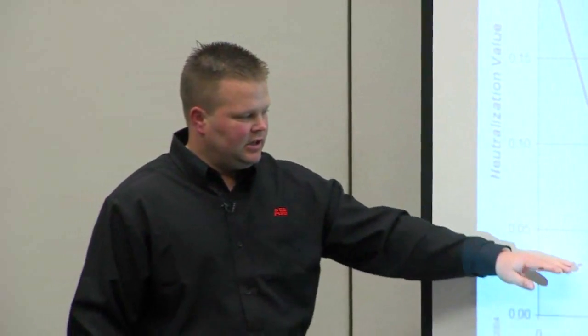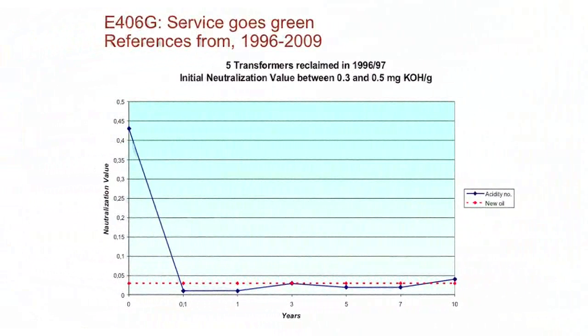So as you can see, over time, after the first month, it was well below the normal acceptable acidity level, and then it increased slightly above the normal, but well within the acceptable limits. Again, the oil started between 0.3 and 0.5. It represents the very same result.